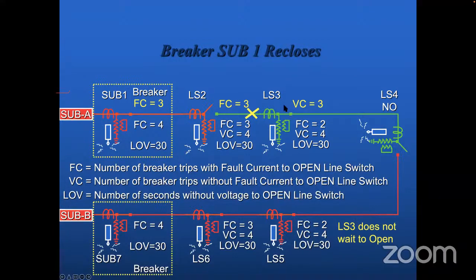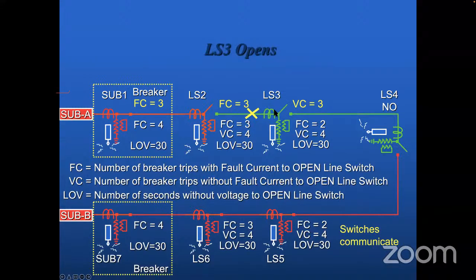LS3, VC3, and now we will have VC4 here. So LOV (loss of voltage) kicks in, 30 seconds without voltage, and then it opens up based on this local decision it is making. It's counting the counter, LOV, no voltage for 30 seconds, it will open, and this automatically removes the fault. So the fault is there, but that line is now not energized at all.